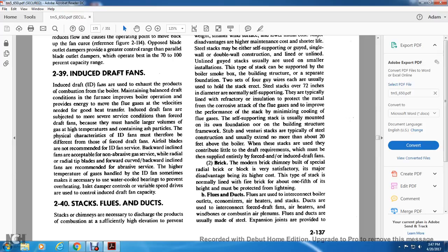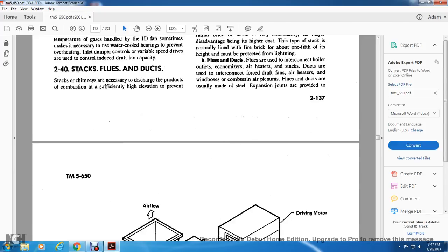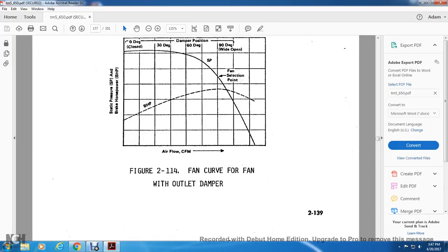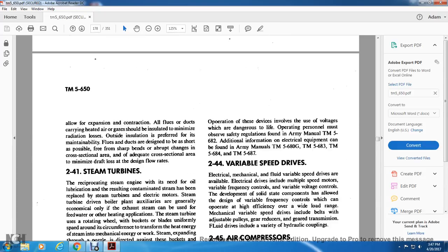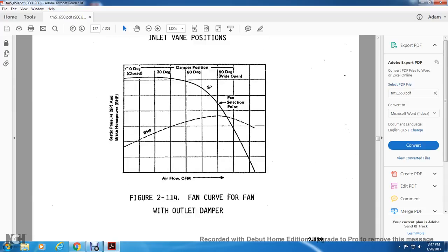Flues and ducts. Flues are used to interconnect boiler outlets, economizers, air heaters, and stacks, and ducts are used to interconnect forced draft fans and air heaters, wind boxes, and combustion air plenums. Flues and ducts are usually made of steel. Expansion joints are provided to allow for expansion and contraction. All flues and ducts carrying hot air or gas should be insulated to minimize radiation loss. Outside insulation is preferred for maintainable flues and ducts, designed with as short a run as possible, free from sharp bends and abrupt changes in cross-sectional area, and of adequate cross-sectional area to minimize draft loss at design flow rates.